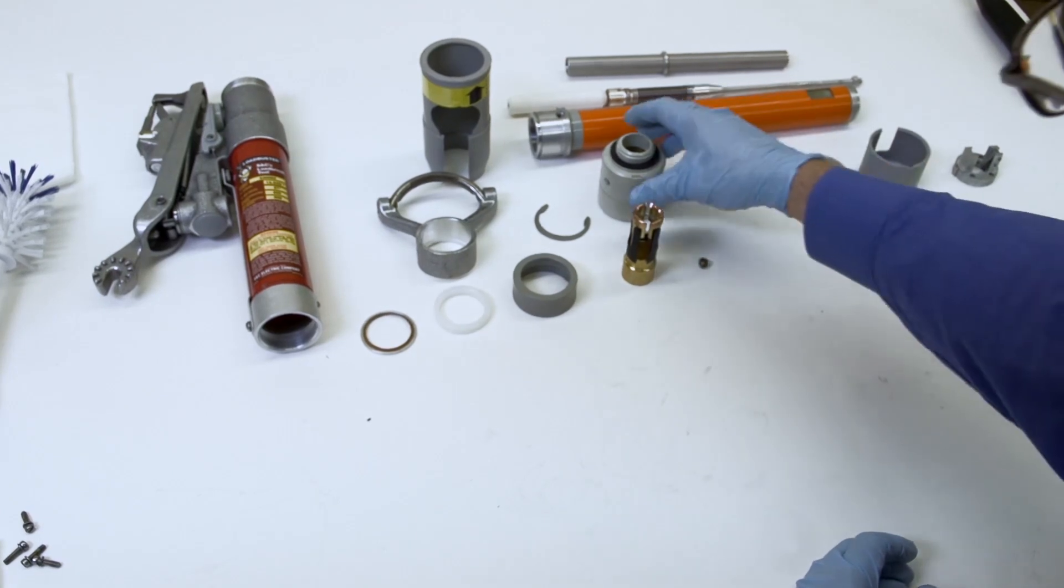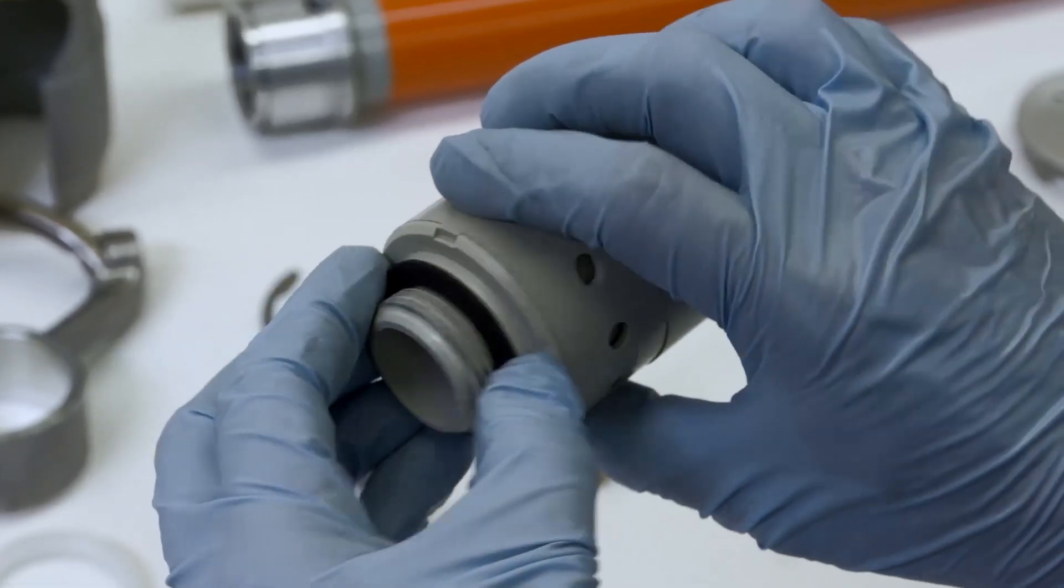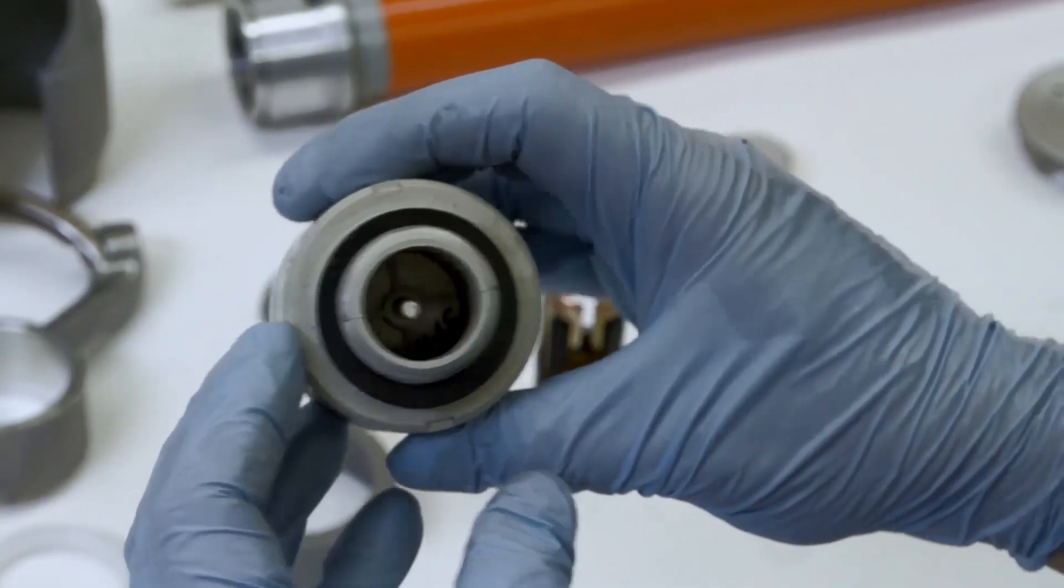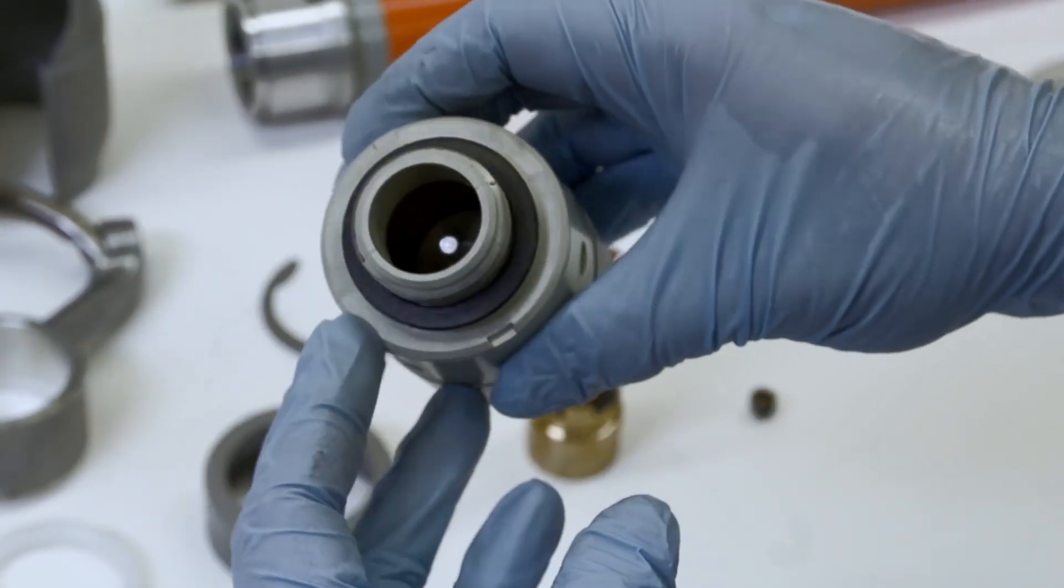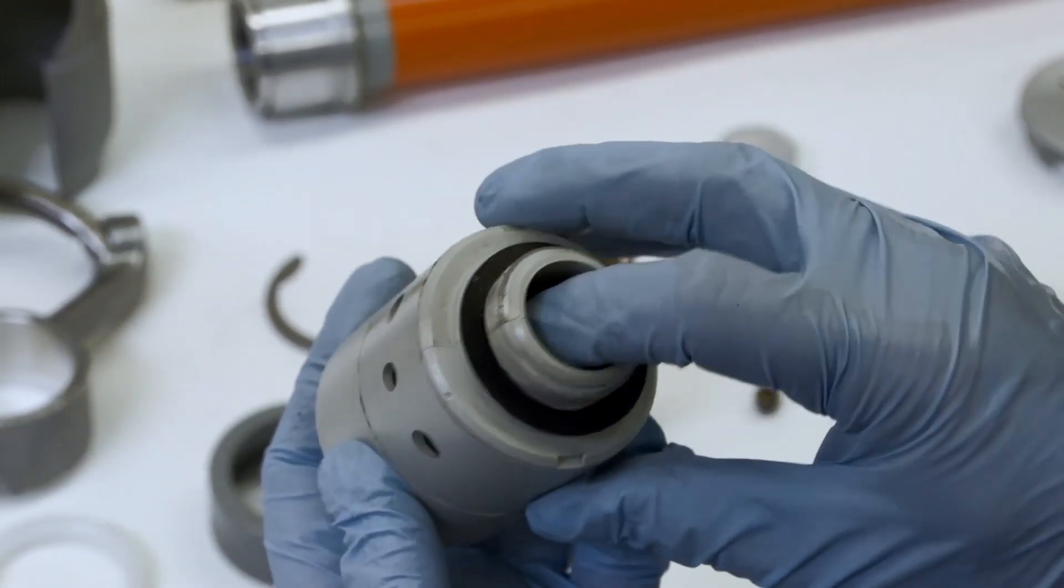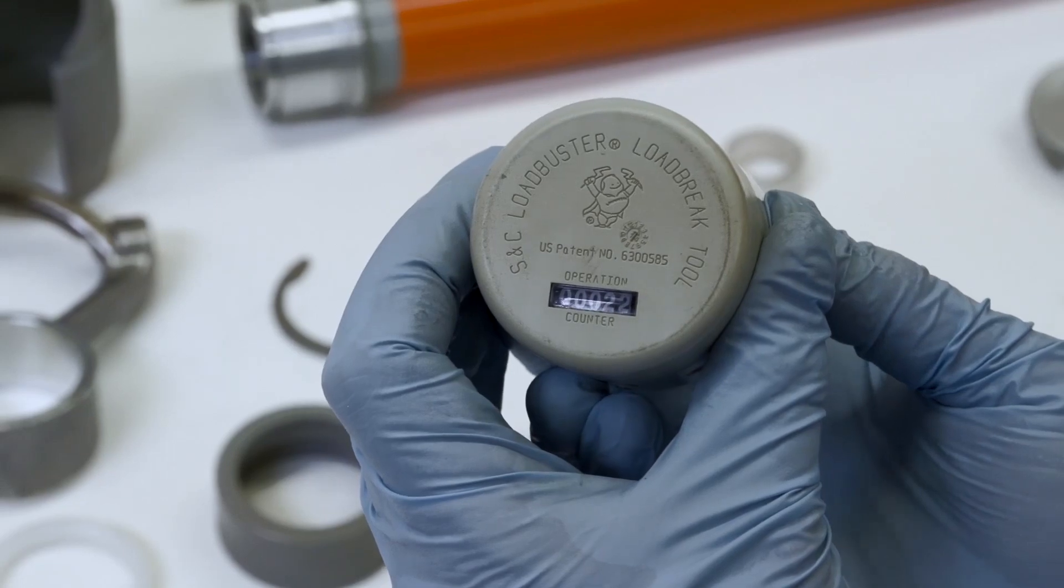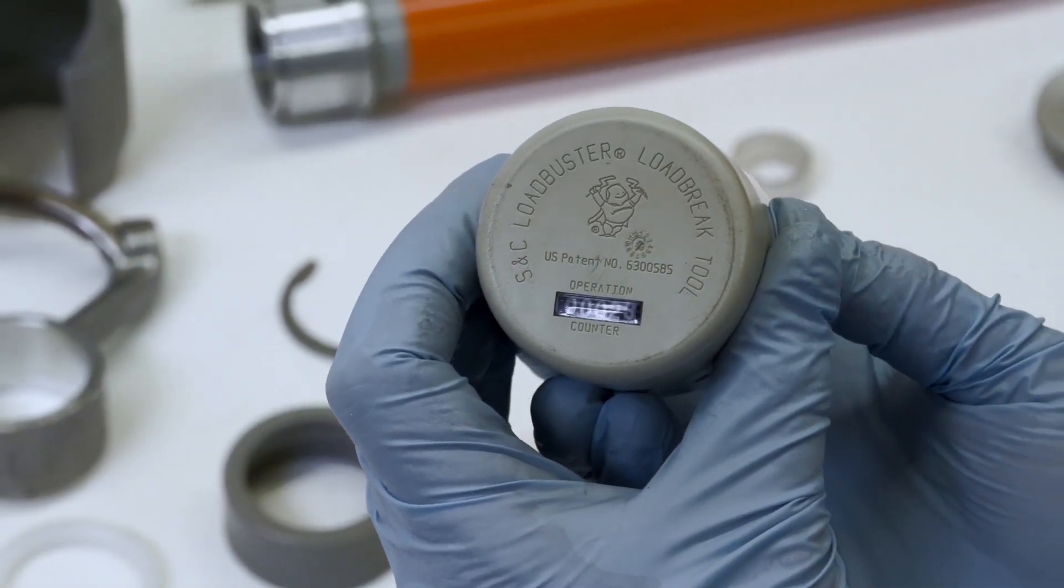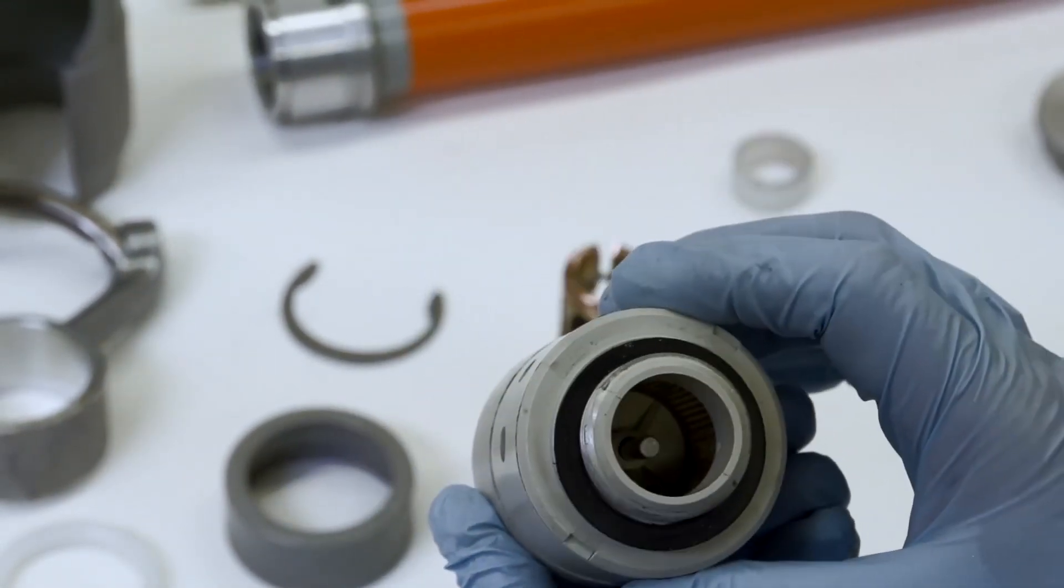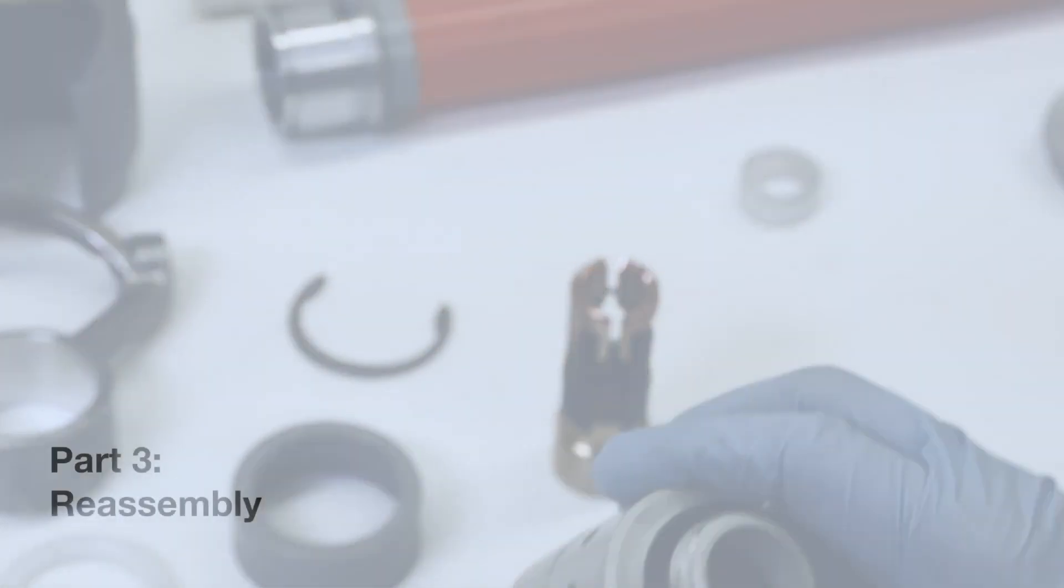Next, inspect the silencer to make sure the gasket, also called the silencer snubber, is in good condition. Look inside for evidence of corrosion or wear. Make sure the mesh is in good condition. Then push the pin to actuate the counter mechanism. Make sure the counter number advances each time the pin is pushed. This concludes the inspection of the Loadbuster Load Break Tool.